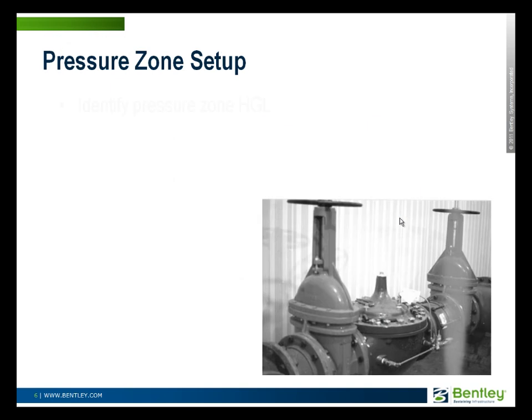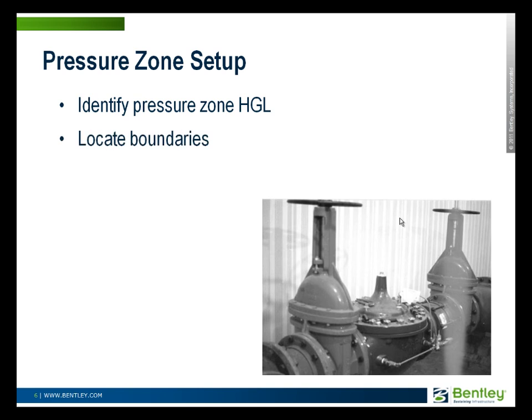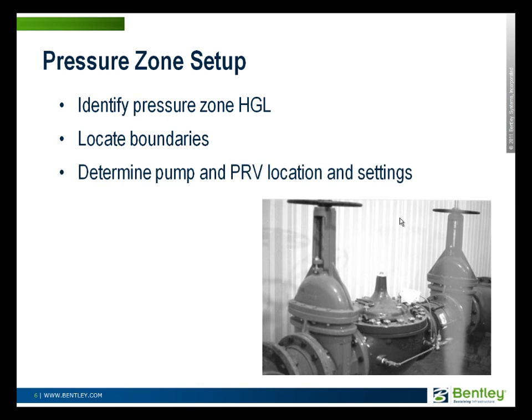There are a lot of other uses. For example, setting up pressure zones — this is the most fundamental problem in water system design: where do you put the pressure zone boundaries? What are the extents of the pressure zones? What hydraulic grade line is going to be maintained in each zone? You locate where the boundary valves are or boundary pump stations, and then you can decide on the location of those valves and pumps and what settings you have for the PRVs, as you see in the picture here, or the pumps between the pressure zones.